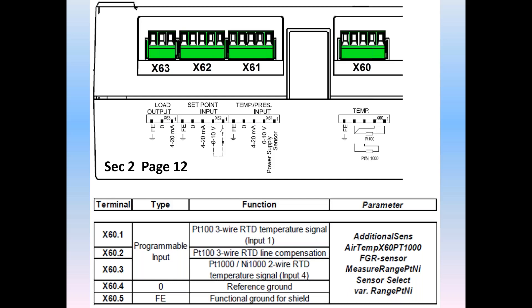This design follows through on all of the LMV-5 terminals. On the side of the LMV-5 are the lower voltage green plugs with a legend showing the pin numbers and the functions. And again, in technical instructions, a table of terminal information. Throughout the instructions, the relationship is shown between terminal, function, and parameter. This is repeated in the manual's text, charts, wiring diagrams, parameter descriptions, and the troubleshooting section. Terminal, function, parameter.